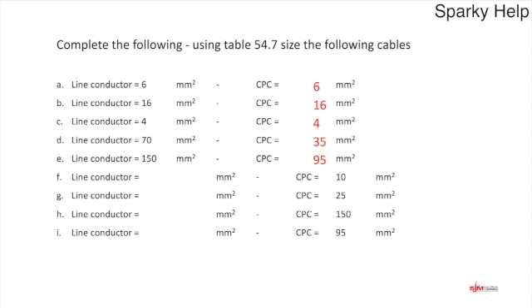So 95 mil would be the size of your earth that would go in for that. I've just turned it on its head. It don't normally work this way, but just to see where you'll go with it. If you had a 10 mil CPC going backwards, therefore the line conductor would also be a 10. If you had a 25 mil, it would be double that size, so it becomes a 50. So you would have a 50 to go with that earth.